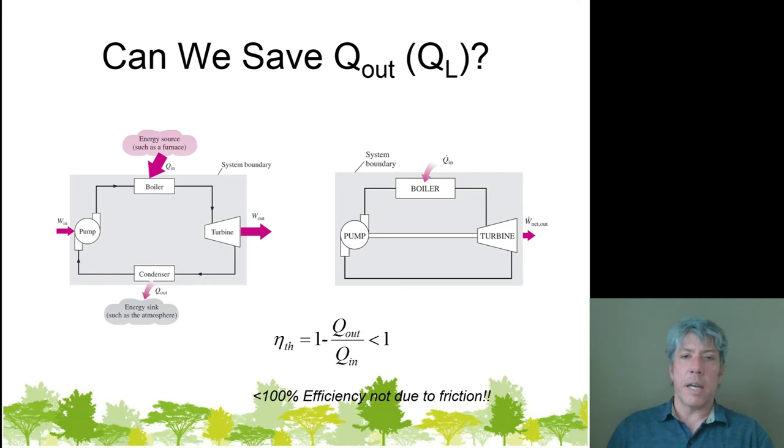Well, it doesn't work because the system will not keep going, basically. One of the things that happens is the steam coming out of the turbine will destroy your pump. The pumps don't like steam like that. It won't work. Now, we can take some of the work produced by the turbine and drive the pump. In fact, that's commonly what's done. But a turbine that produces a couple hundred megawatts can easily produce enough power to drive a pump that only requires maybe 70 to 500 kilowatts. That's a small fraction. So back driving the pump, that's no big deal.